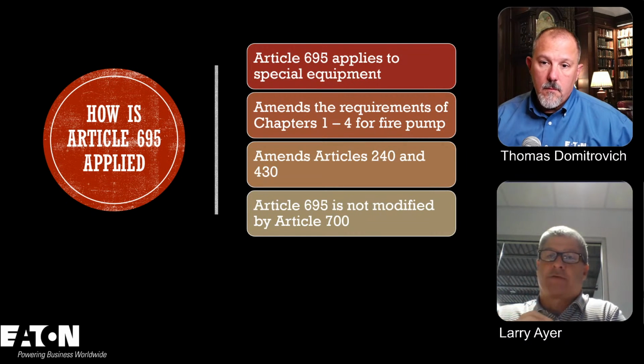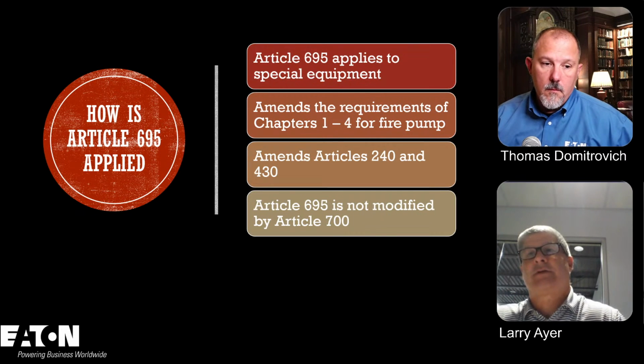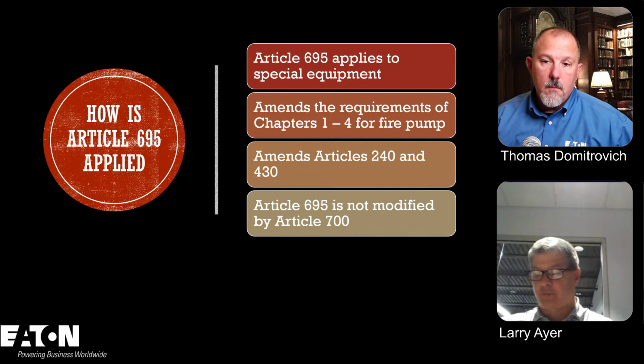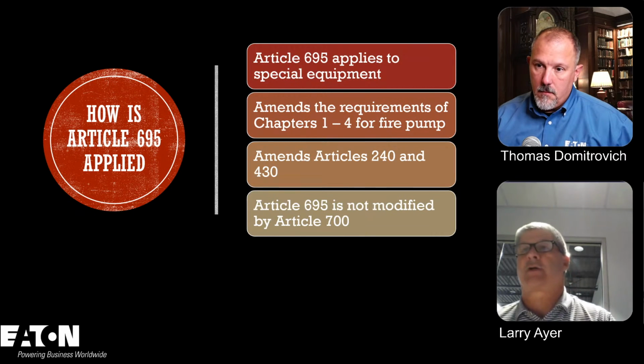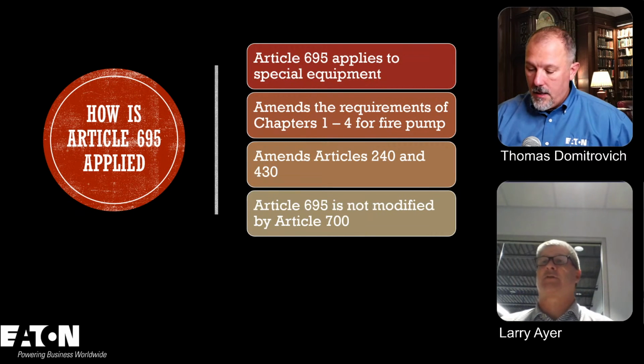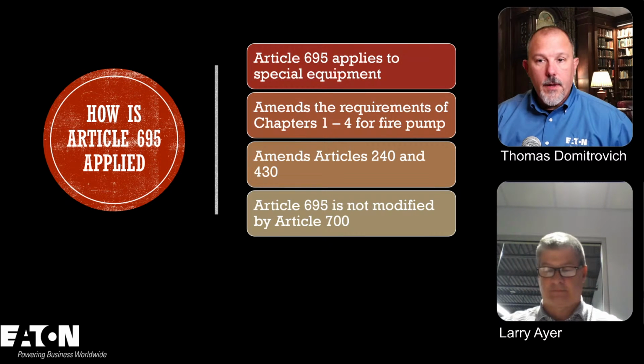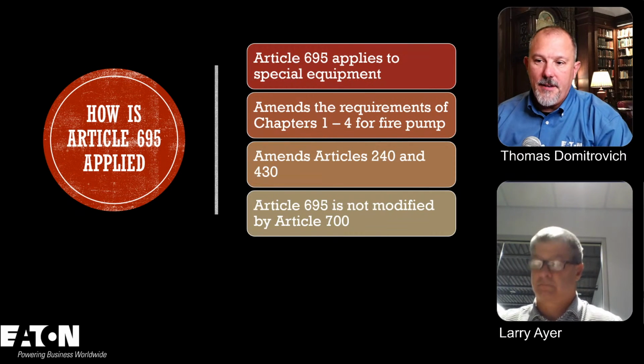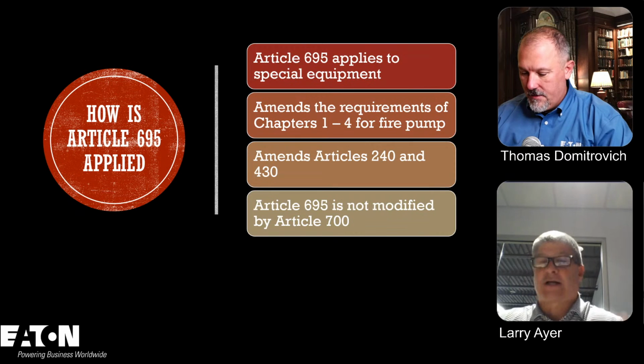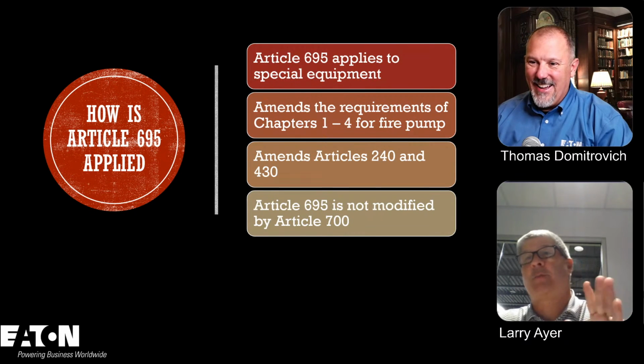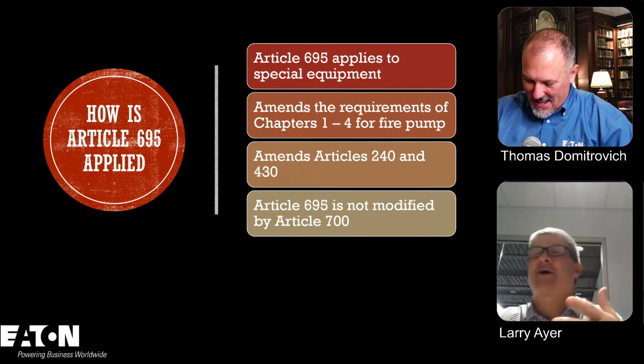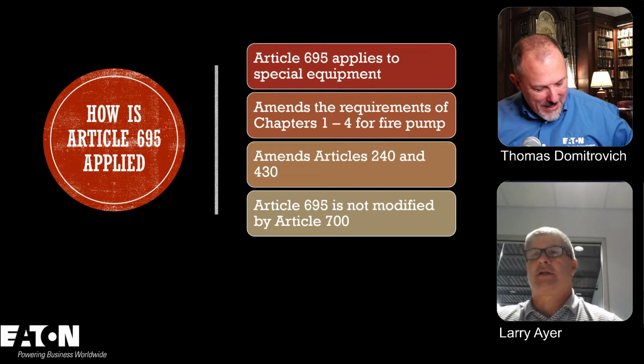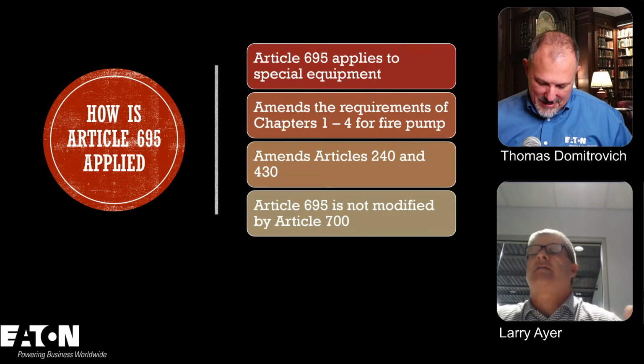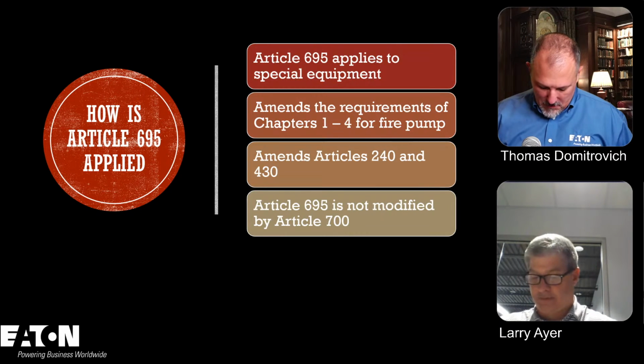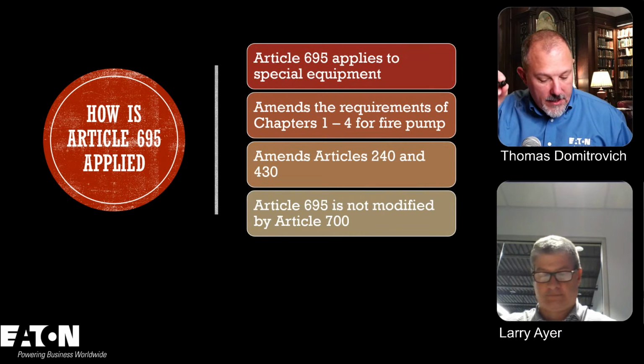And one of the other things that you want to talk about: the question is what article covers jockey pumps. When you look at 695, it doesn't really mention jockey pumps. They basically refer to them as fire pump accessory equipment. So they use a different terminology than that. Okay, so you're not going to find the term jockey pump in 695. Correct. Now, someone's going to go look and they're going to find it once. But when they talk about feeders, and when you size things, they talk about fire pump accessory equipment. Now you are on the record as saying there's no jockey pump in there.